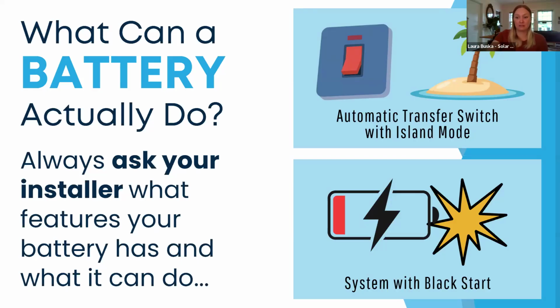Having black start is important because if your outage is prolonged, the battery may drain completely, and black start allows your system to restart from a completely dead state during that outage. Once the sun rises, the battery detects incoming sunlight and uses that tiny reserve to wake up the system, tricking it into thinking the grid is back online. Then it begins producing power and sending excess to recharge that battery.